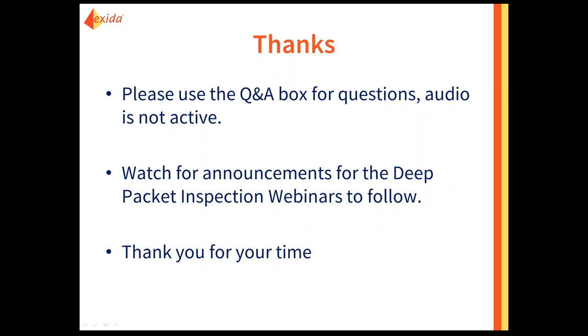Q: SCADA and DCS have dozens of protocols — A: Yes they do, but I'm talking about the protocols getting down to end devices like a PLC, which is usually a very limited set. I'm not talking about an edge firewall, which does have many protocols. When you're talking about a PLC or end device, which is where these firewalls are intended to go, the communications are very limited in what protocols they use.